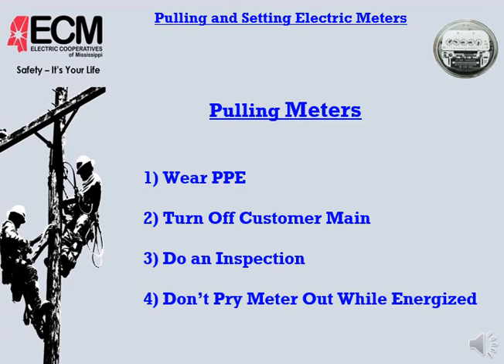We do our inspection process to make sure we don't have that problem, so we're not pulling it and creating a fault or a trap for ourselves. Don't pry at the meter while it's energized. If it's been there a long time it may be stubborn and take a little force to pull, but it shouldn't take a whole lot.